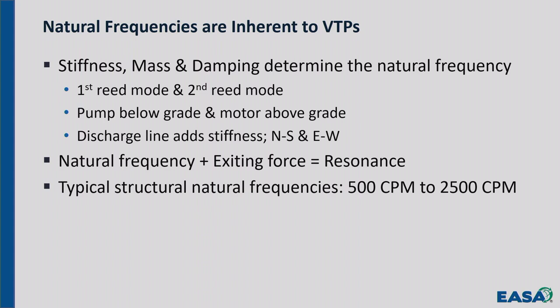So we've got potential resonance at 2 different reed frequencies on the motor, 2 different reed frequencies on the pump, north-south, east-west, really close to operating speeds. Why don't we just put it on a variable frequency drive? And if you can't find a resonant frequency at a synchronous speed, put a VFD on it. You'll find it. It'll be there. It'll be just exactly the speed that the customer wants to run the pump at.